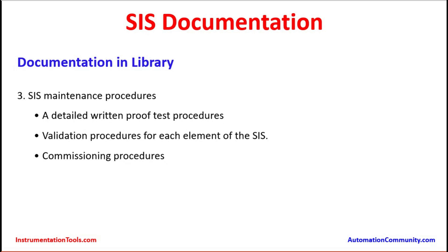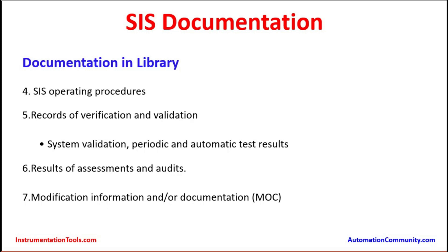Detailed proof test procedures, validation procedures for each element of the safety instrumented system, and commissioning procedures are documents that also need to be maintained in the library for future reference. SIS operating procedures and records of verification and validation — including system validation, periodic and automatic test results, and results of assessments and audits — must be kept. Modification information and documentation must also be maintained through the MOC (Management of Change) system: any modification done on an SIS loop must be documented and pass through the MOC system, which requires different levels of approval.